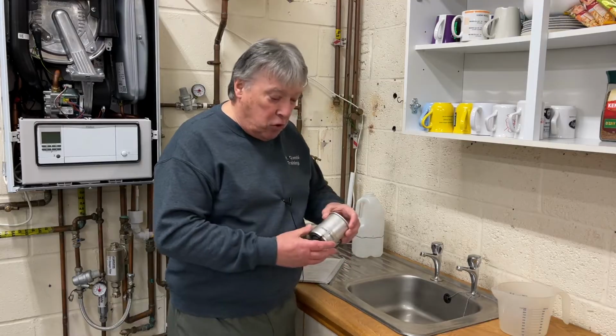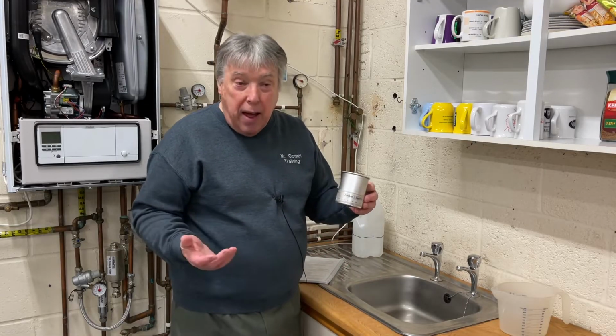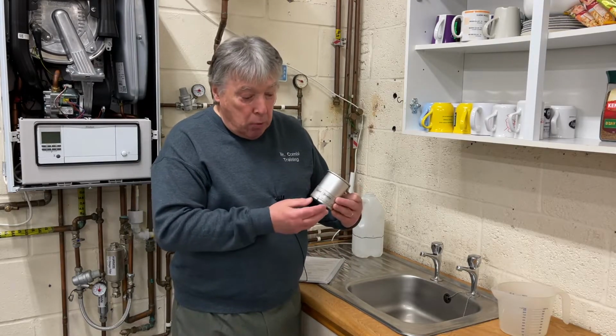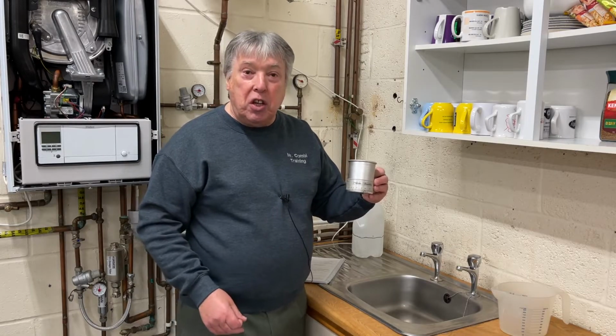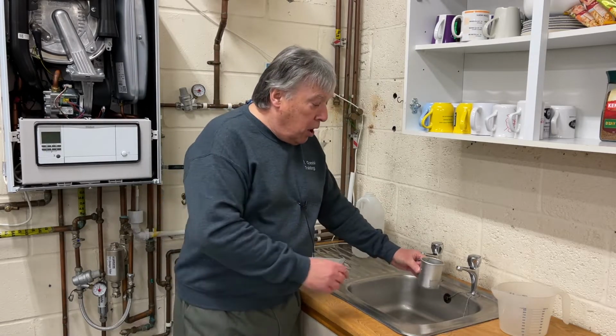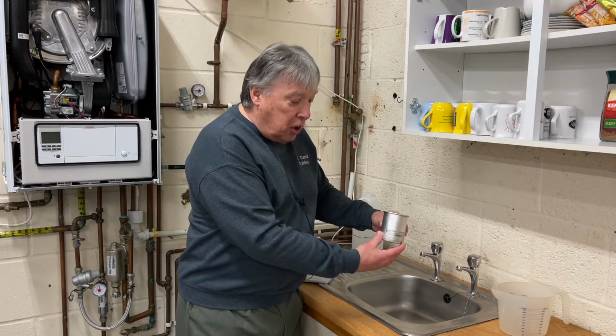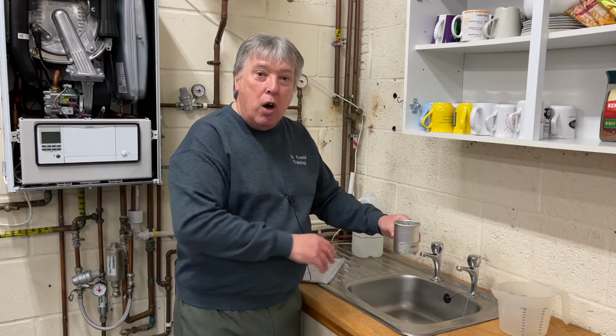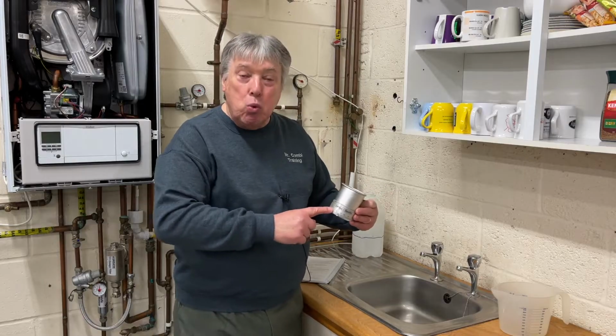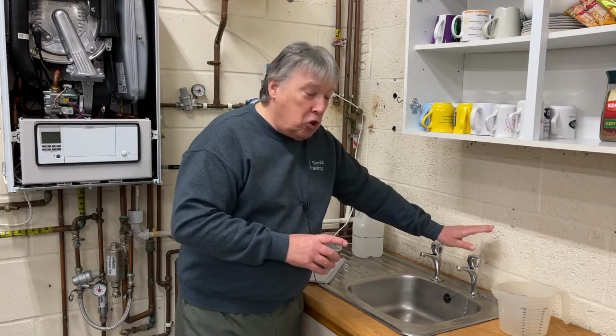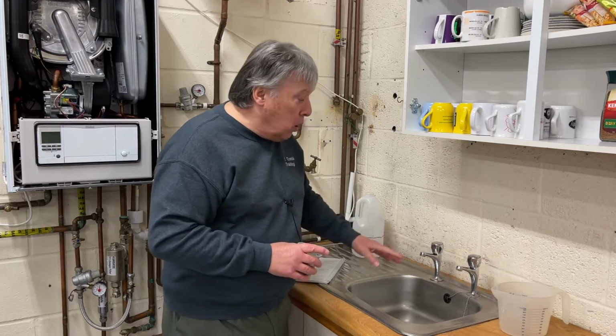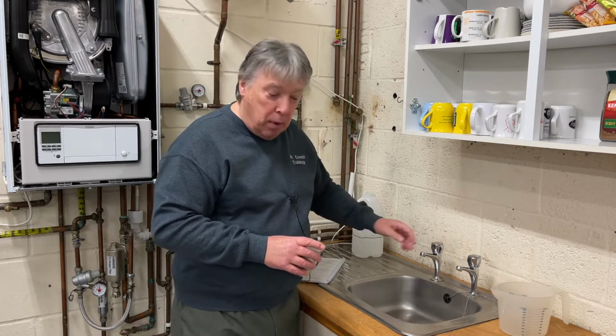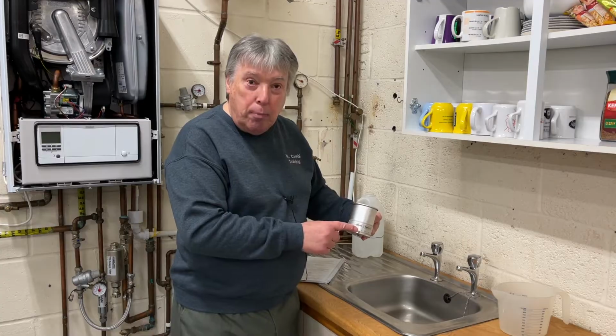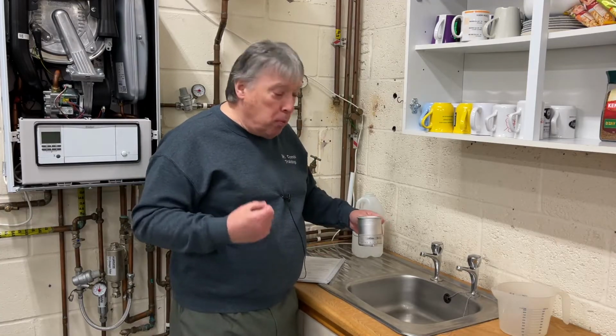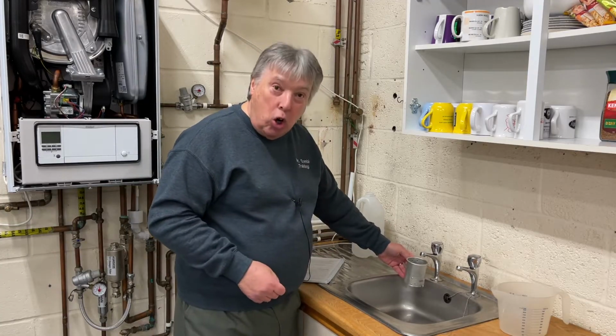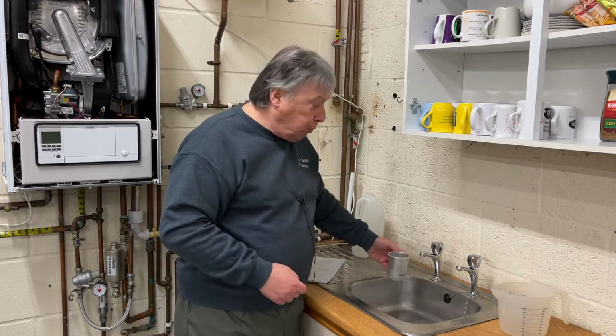The best way for installers, which you should have, is a weir cup. And again, we'll put this on somewhere high, maybe at 16, underneath the cold tap, and we're looking to gradually lower this down so the water doesn't quite overflow, and that's our incoming water main. And then we can turn the cold tap off. Now we repeat the process with the hot tap. So that will be higher because obviously there's going to be resistance in the boiler. So we can put this underneath the hot tap, turn it on full.